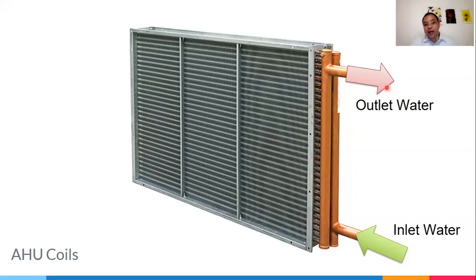Sa ilalim, inlet. Sa ibabaw, outlet. Why does the inlet water have to be on the bottom and the outlet on top? Because when you fill the coil with water, if you start from the top, some areas won't be filled and bubbles will be retained. If you inject water from below, it fills up from the bottom first and rises, ensuring you purge out the air inside the coil efficiently. So that's the reasoning why inlet is at the bottom and outlet is at the top - to ensure your coil is filled with water, not bubbles.